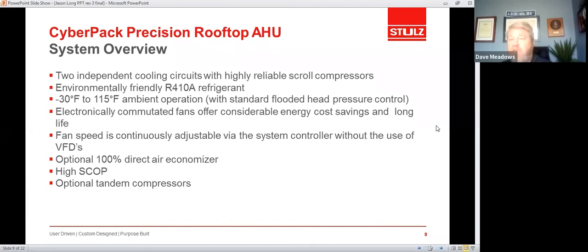One of the other things that sets a rooftop CRAC apart from its comfort cooling brothers is that it has a high SCOP. That stands for sensible coefficient of performance. This is the metric that would be the equivalent of EER in a comfort cooling piece of HVAC equipment. The only major difference between SCOP and EER is that the SCOP uses like units as opposed to different units that you have in the EER. And also we get no credit for any latent cooling that the piece of equipment does.